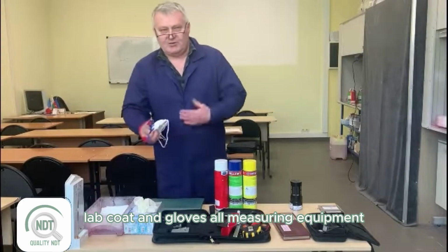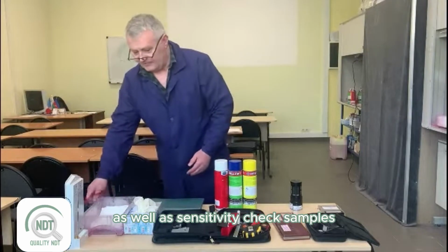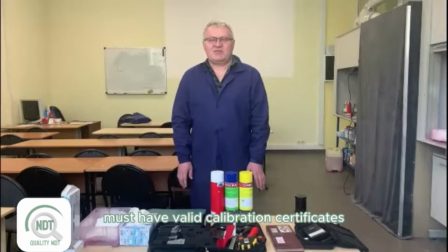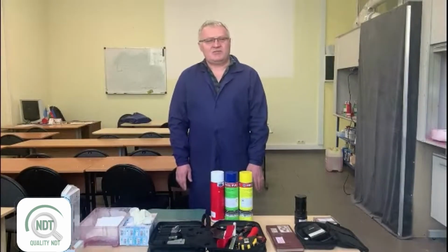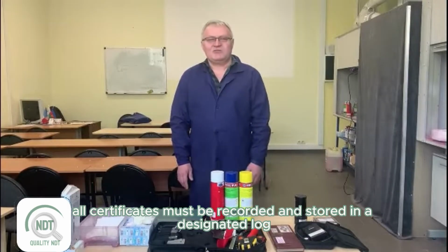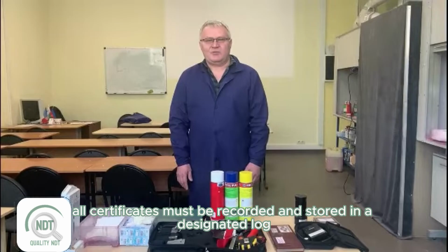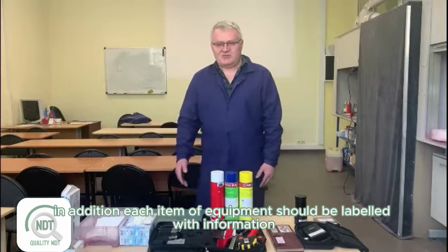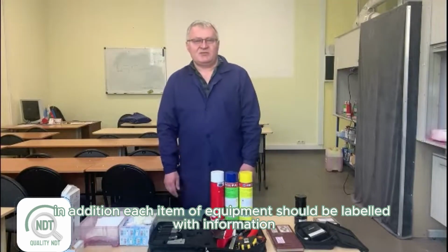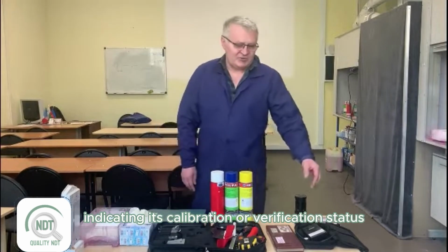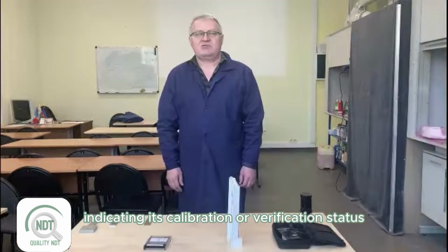All measuring equipment, as well as sensitivity check samples, must have valid calibration certificates. All certificates must be recorded and stored in a designated log. In addition, each item of equipment should be labeled with information indicating its calibration or verification status.